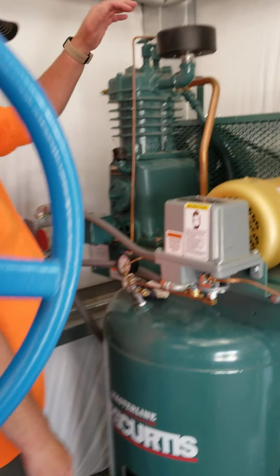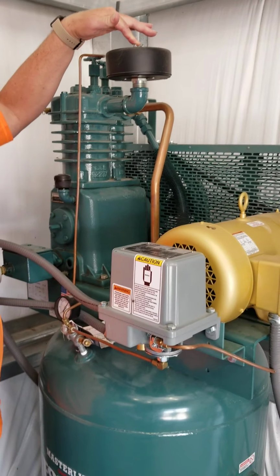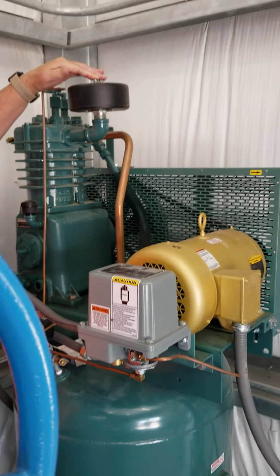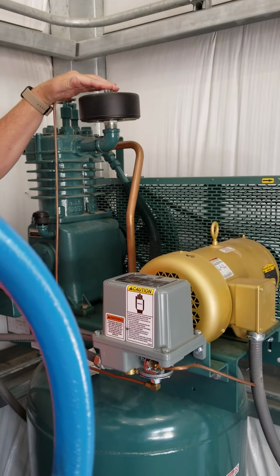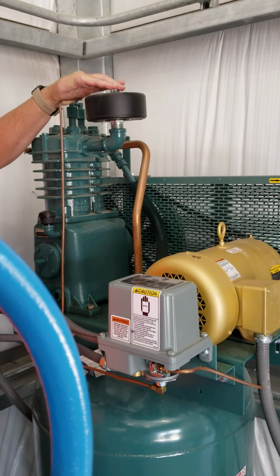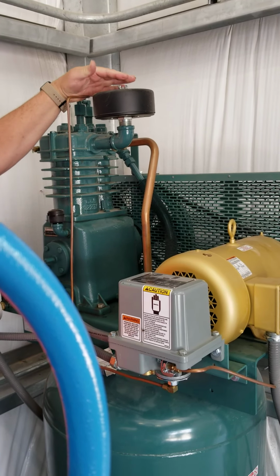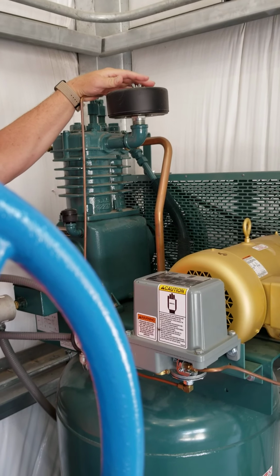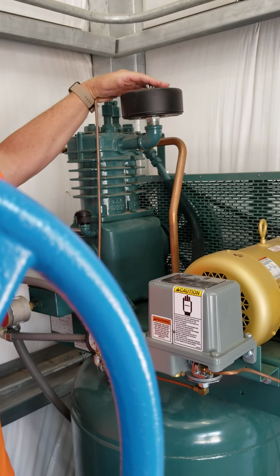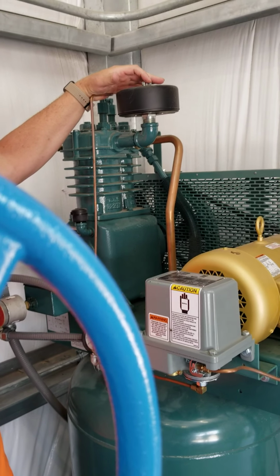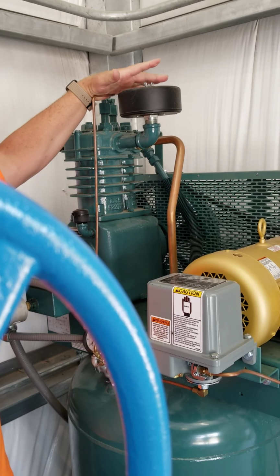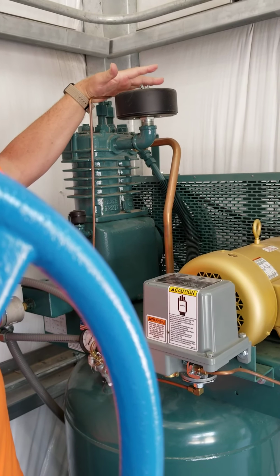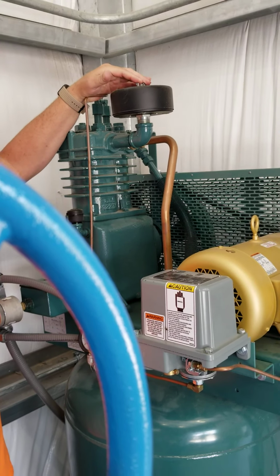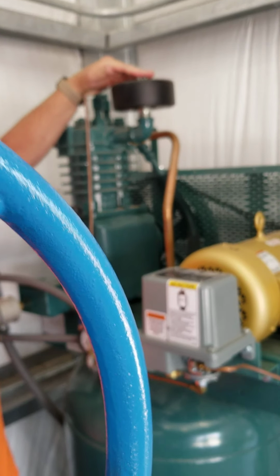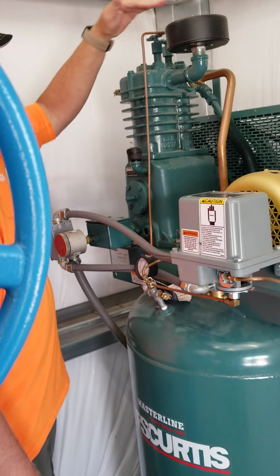On the top of the unit, you have an intake air filter. The intake air filter should be taken off. I typically recommend in the very beginning, maybe once a week, you can blow it off, clean it off, and then replace it. If you wash it, you obviously need to make sure it's dry before you put it back on. Once the room gets clean and doors are shut, you can probably change this to once a month, every couple months, and that'll be something you need to look at as far as how often you need to clean that filter.